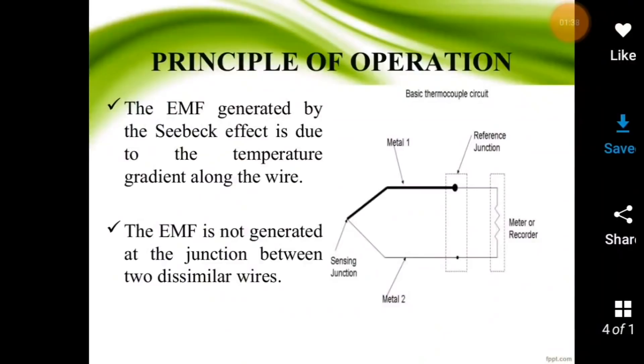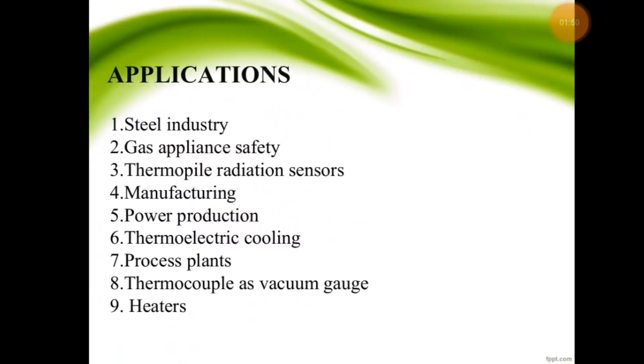Principle of operation: the EMF generated by the Seebeck effect is due to the temperature gradient along the wire. The EMF is not generated at the junction between two dissimilar wires. Applications include steel industry, gas appliance safety, thermopile radiation sensors, manufacturing, power production, thermoelectric cooling, process plants, thermocouple as vacuum gauge, and heaters.